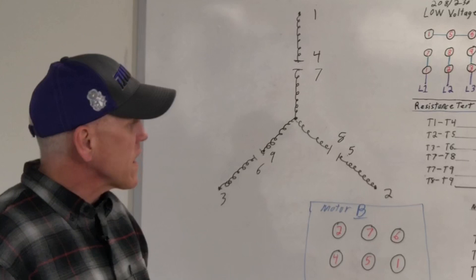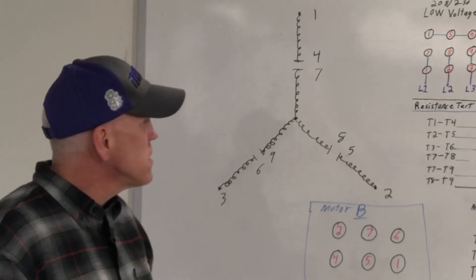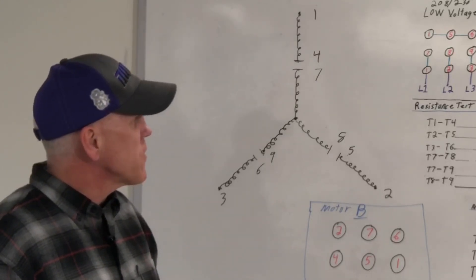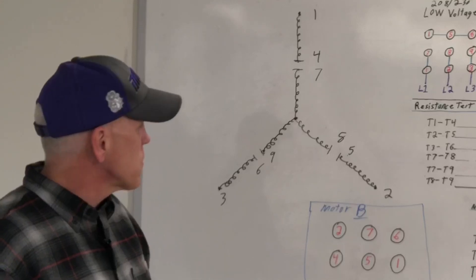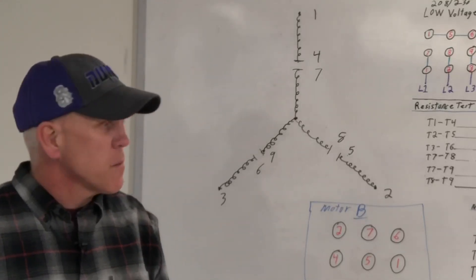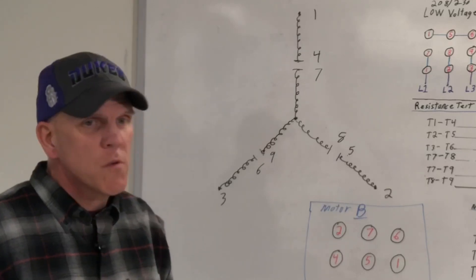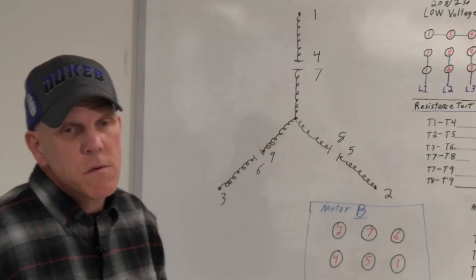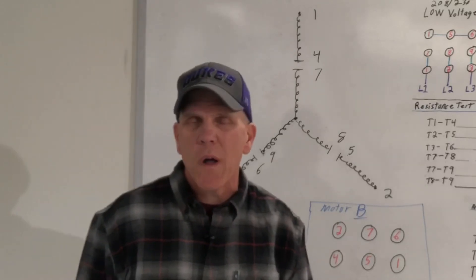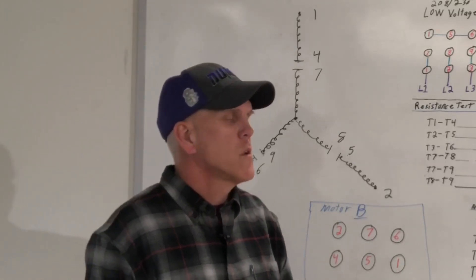I can't think of anything else to tell you. And I might say everything went real well. All the motors are up and running. Their overloads are back the way they're supposed to be. I may talk to them, maybe in the future throw some phase monitors on them. Just some motor watchers or whatever, motor savers, whatever they may be. They're pretty cheap.